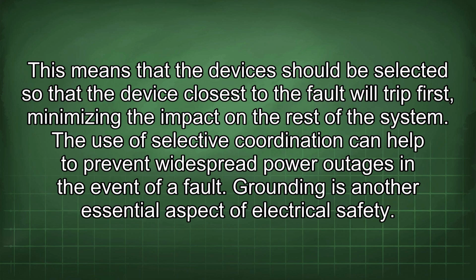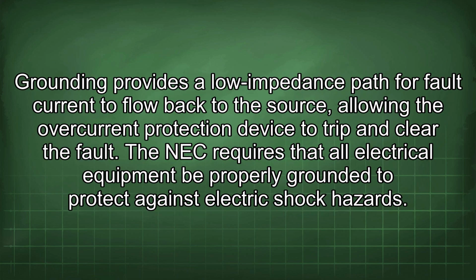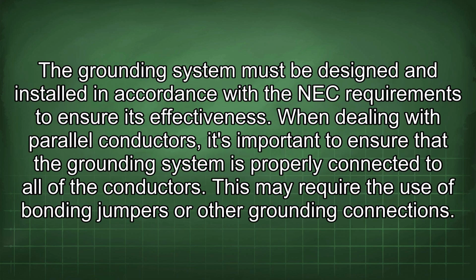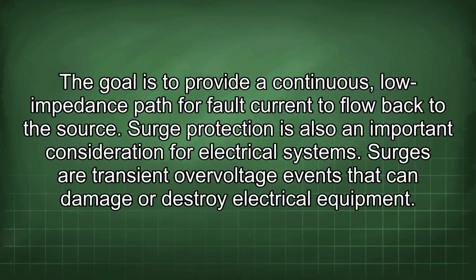Grounding is another essential aspect of electrical safety. Grounding provides a low impedance path for fault current to flow back to the source, allowing the overcurrent protection device to trip and clear the fault. The NEC requires that all electrical equipment be properly grounded to protect against electric shock hazards. The grounding system must be designed and installed in accordance with the NEC requirements to ensure its effectiveness. When dealing with parallel conductors, it's important to ensure that the grounding system is properly connected to all of the conductors. This may require the use of bonding jumpers or other grounding connections. The goal is to provide a continuous, low-impedance path for fault current to flow back to the source.